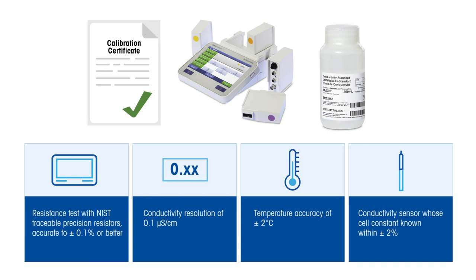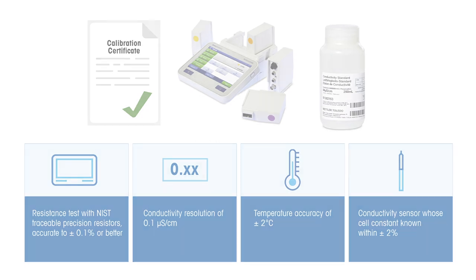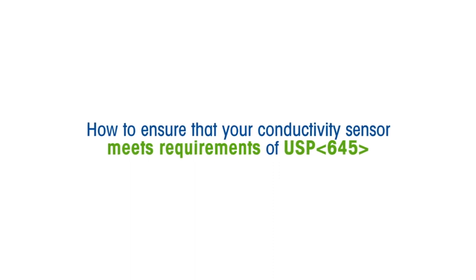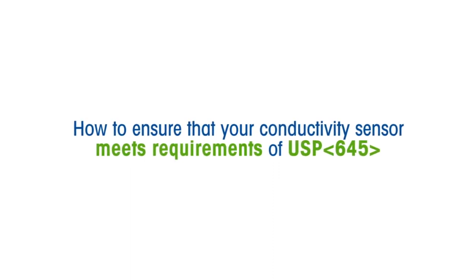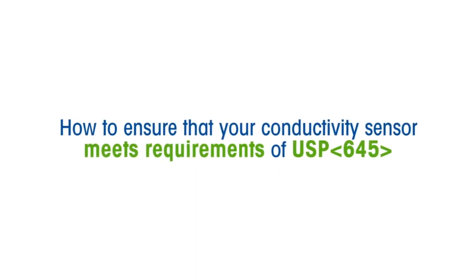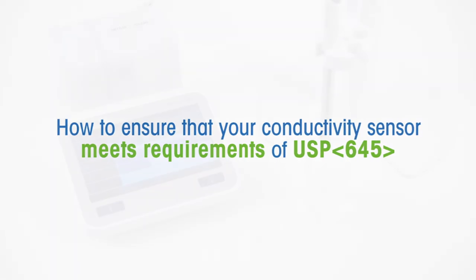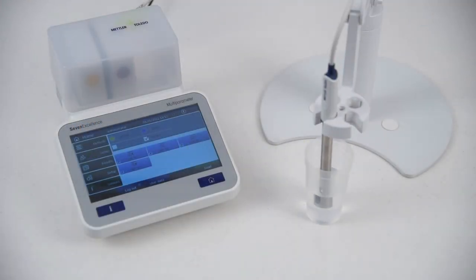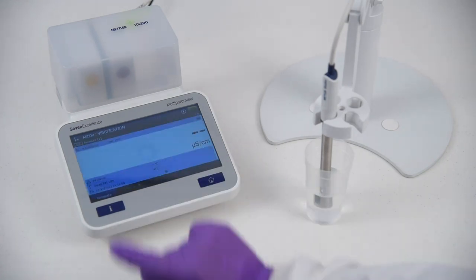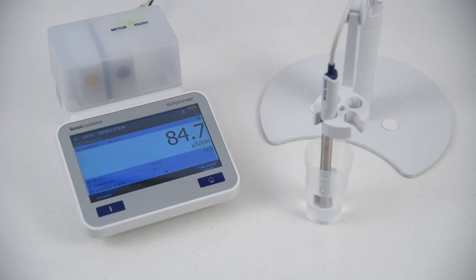This can be verified using a solution of known or traceable conductivity solution. This procedure will show you how to ensure that your conductivity sensor meets the requirements of USP645. If the conductivity sensor you use has a certified cell constant, only a verification in a low conductivity standard is required.